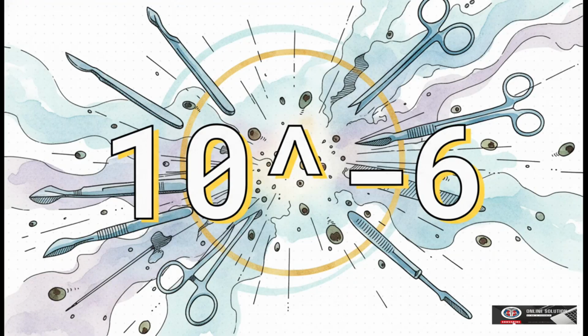Okay, so 10 to the negative sixth. It looks like just a random number, right? But this is actually the probabilistic holy grail for critical surgical instruments. See, unlike disinfection, sterilization is intended to be absolute. But here's the catch. We can't actually prove the absence of every single microbe without completely destroying the item we're trying to test. So how do we guarantee safety?